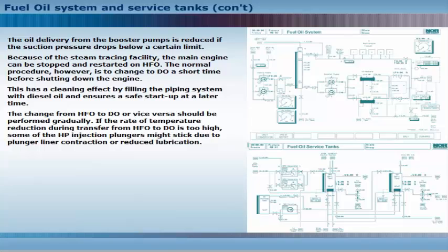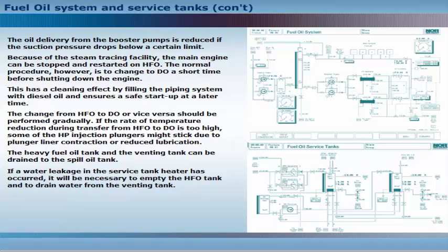The change from heavy fuel oil to diesel oil, or vice versa, should be performed gradually. If the rate of temperature reduction during transfer from heavy fuel oil to diesel oil is too high, some of the high-pressure injection plungers might stick due to plunger liner contraction or reduced lubrication. The heavy fuel oil tank and the venting tank can be drained to the spill oil tank. If a water leakage in the service tank heater has occurred, it will be necessary to empty the heavy fuel oil tank and to drain water from the venting tank.